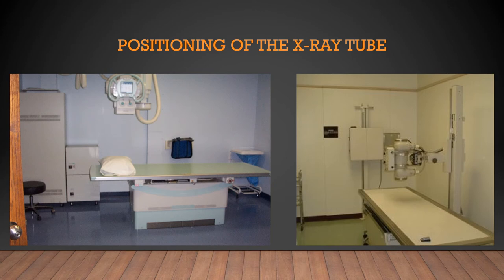This picture shows two ways your x-ray tube can be supported in the room. The first is a ceiling-mounted tube support, also known as a ceiling crane or tube hanger — it suspends the x-ray tube from a system of tracks, allowing it to be moved to all locations throughout the room. The second, more commonly seen in a clinic, is a tube stand: a vertical support with a horizontal arm that suspends the tube over the radiographic table. The tube stand rolls along a track secured to the floor, and sometimes also to the ceiling or wall, parallel to the x-ray table.